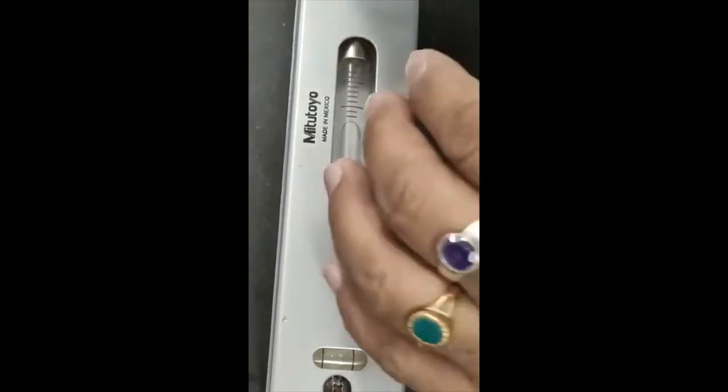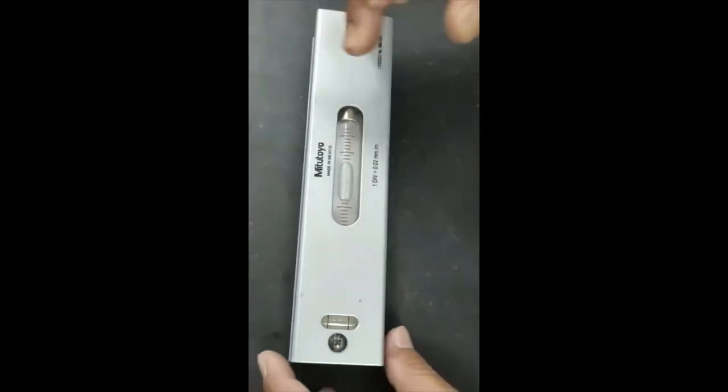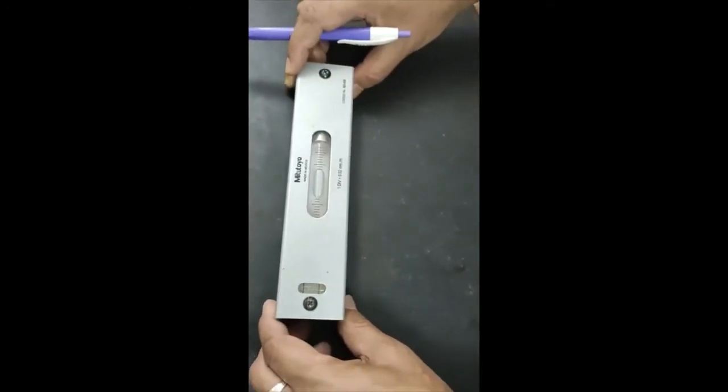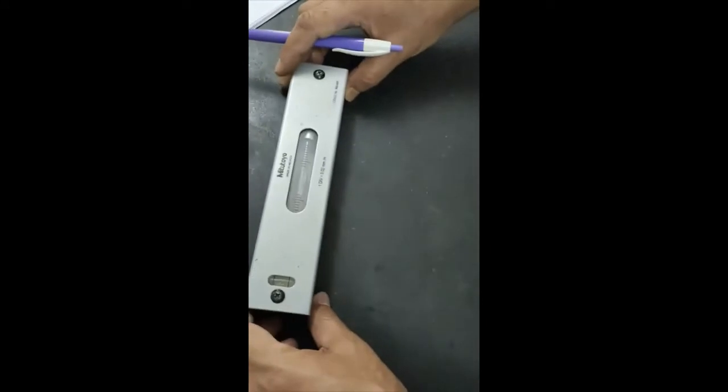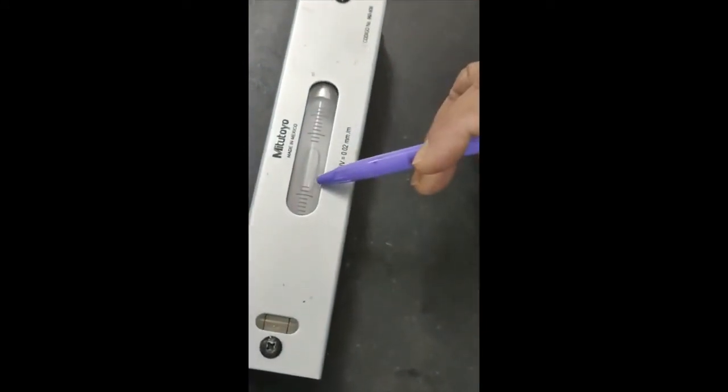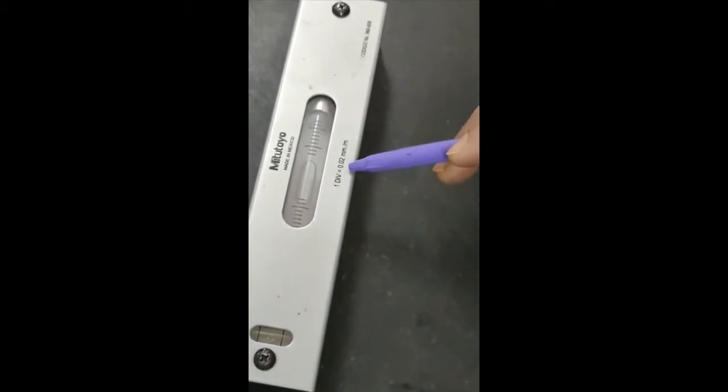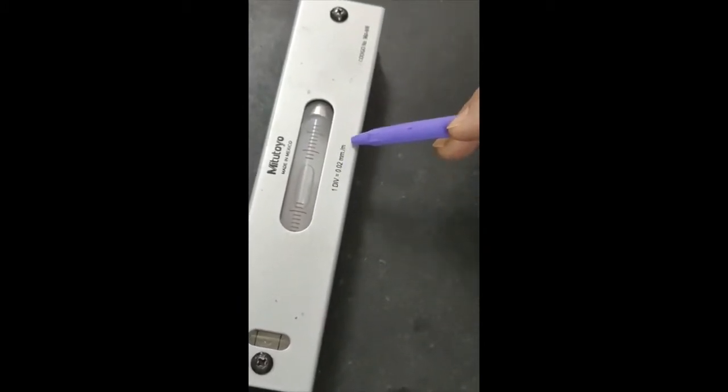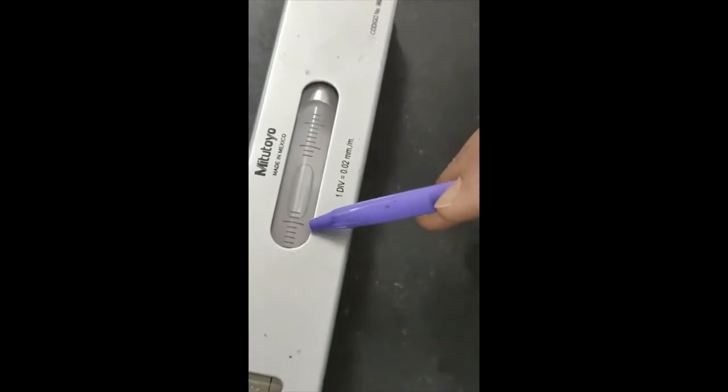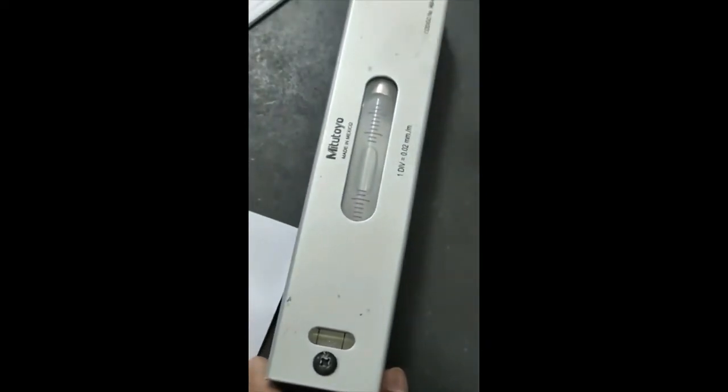If you displace it to different levels, suppose this position is my zero, and after this you can displace it to check its elevation. Now it is coming two divisions. One division means 0.02 millimeter per meter inclination, so two divisions means two into 0.02 inclination.